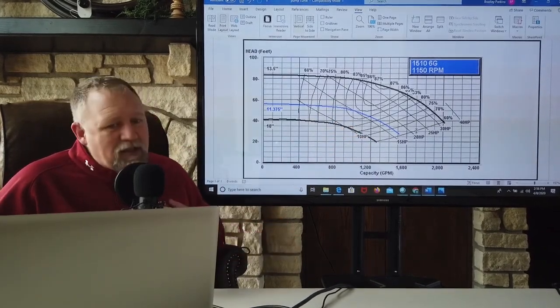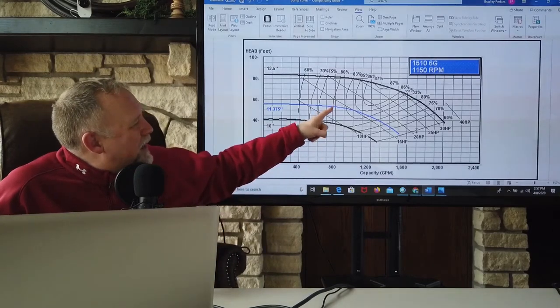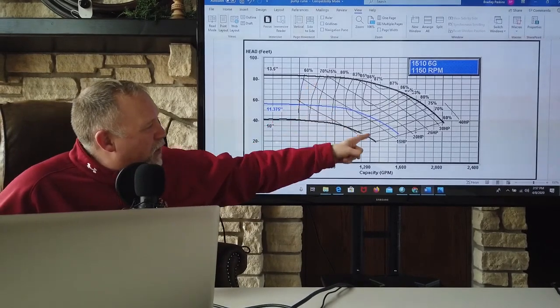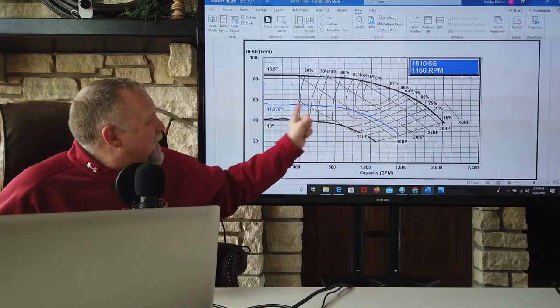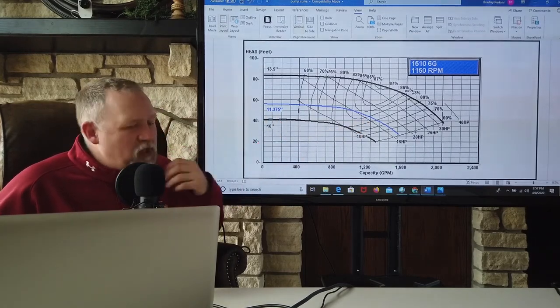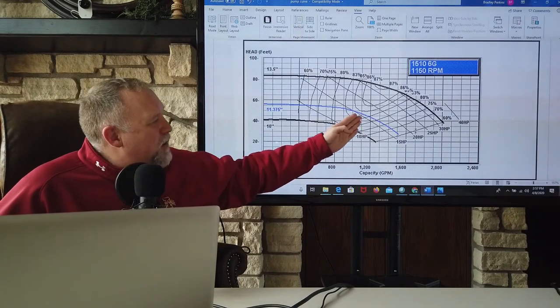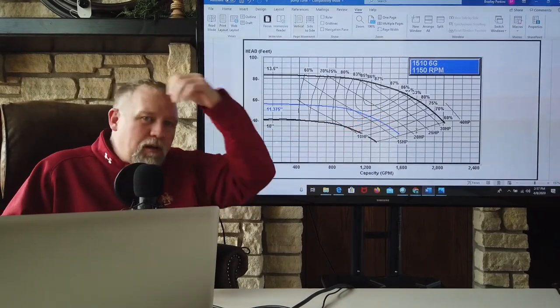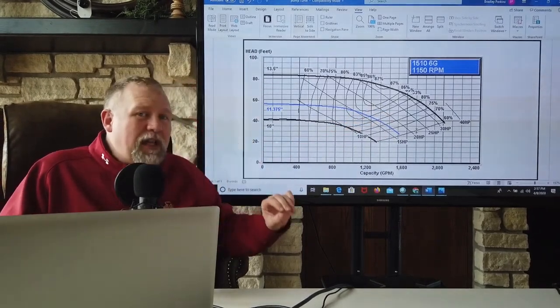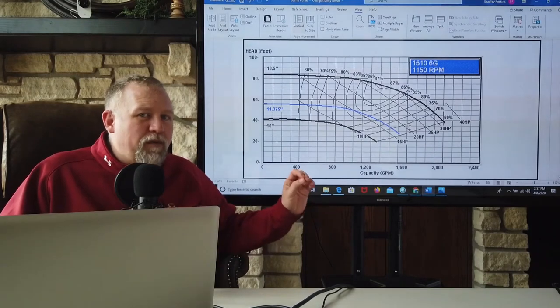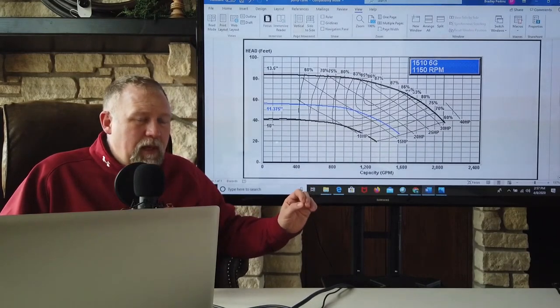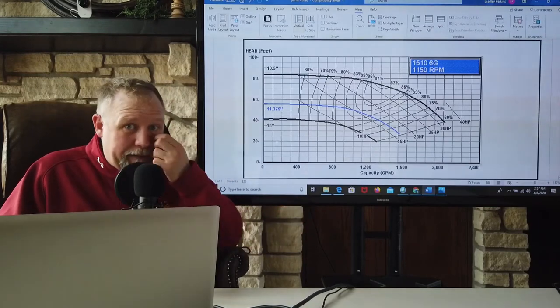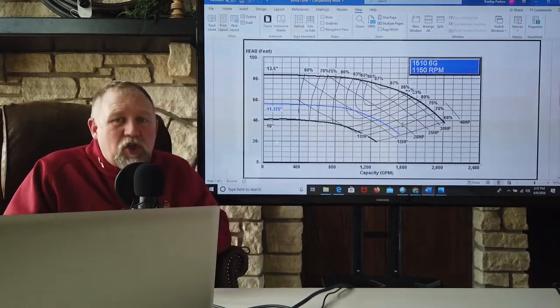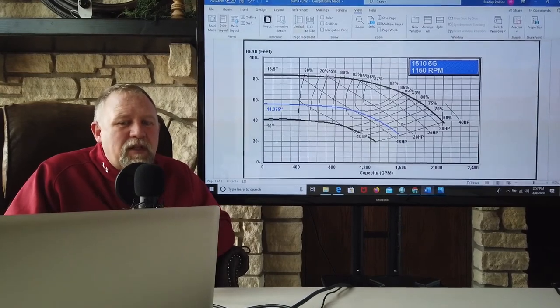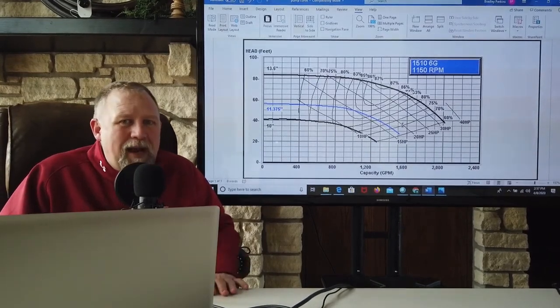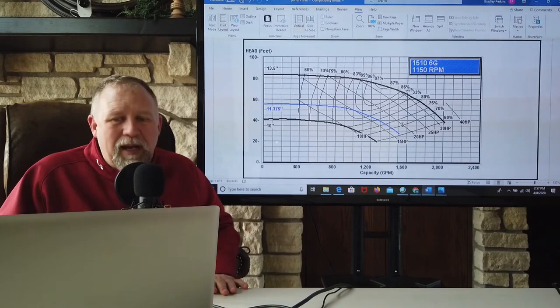Do not do that. As a cautious engineer, even if I was operating here, if the 15 horsepower motor intersected this 11.375 inch impeller at any point, I would go up to the next larger motor size. You're not going to overload a motor by oversizing it. Yes, it might be a little more expensive. However, you're going to ensure that it never even comes close to operating at its operating duty point.